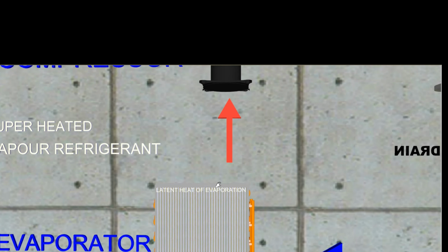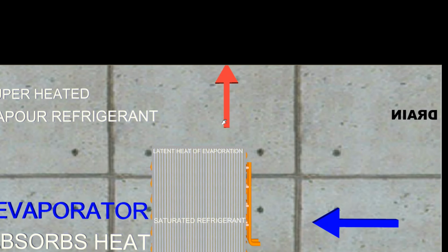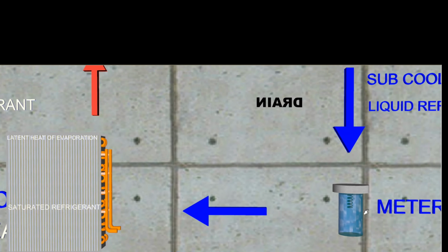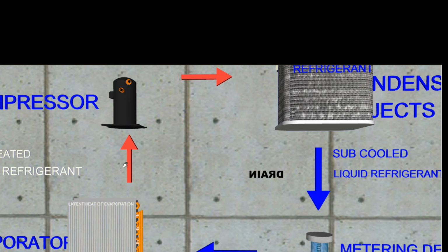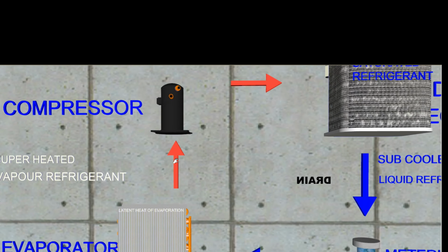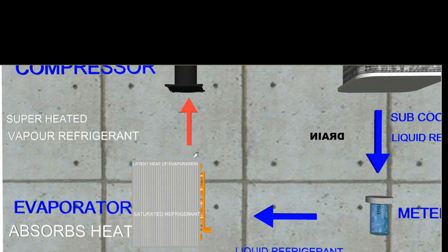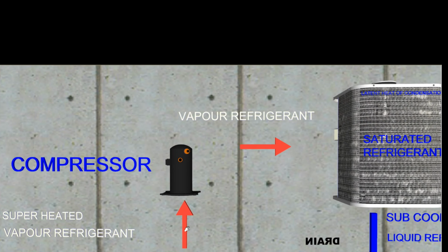So when it leaves the evaporator, it has to be a vapor. And this device over here, this TXV valve, actually ensures that. It has another copper tube that is tied into the suction line right over here, has a little bulb on it, and it senses the vapor coming out. It makes sure only vapor is coming out, because if liquid comes out of the suction line and goes into the compressor, it's going to freeze up or ruin the compressor. We do not want liquid in the compressor, only vapor. So that's what comes out of it, and then the vapor goes in.